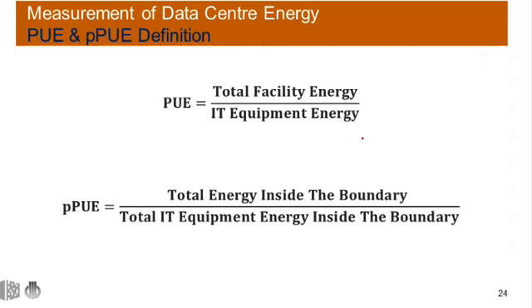PUE was originally defined by the Green Grid back in 2007, and fundamentally it was developed with the objective being to improve the resource efficiency of IT and data centers as a whole. PUE is an annualized metric, so we consider kilowatt hours or megawatt hours rather than kilowatts. So the measurements are taken over 8760 hours per year. PUE can never be less than 1, the 1 being the IT load.